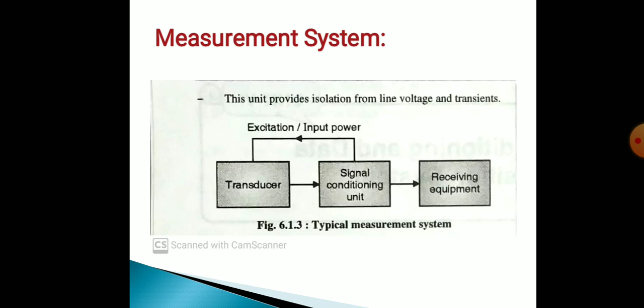Use of signal conditioning circuit. The signal conditioning circuit is used for converting transducer signals of various signal strengths to a standard voltage or current format used for transmission. Standard voltage output signals are 0 to 5 volt and 0 to 10 volt DC, and standard current output signals are 0 to 20 milliampere and 4 to 20 milliampere. The signal conditioning circuit gives the 0 to 5 volt and 0 to 10 volt DC, 0 to 20 milliampere and 4 to 20 milliampere current.